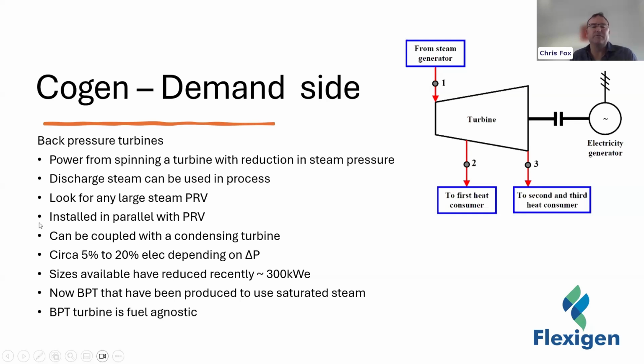They're often or almost always installed in parallel with the pressure reducing station. What that does is it gives you the ability to basically control how much power you want out of the turbine. So if your electrical needs are lower than the output of the turbine, then part of the steam flow goes through the turbine and part goes through the PRV, and so on and so forth. And you just have a control valve which will divert steam either way based on your process needs.